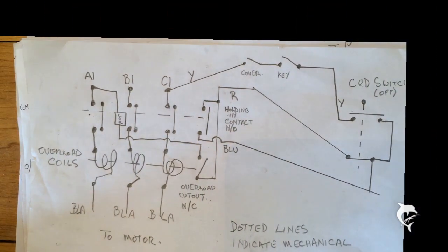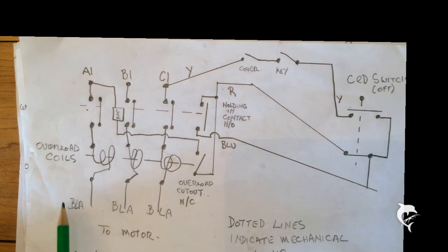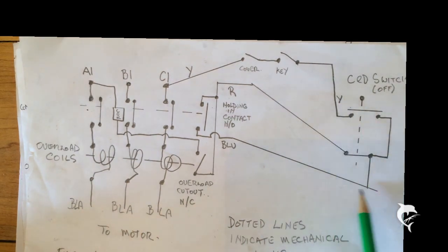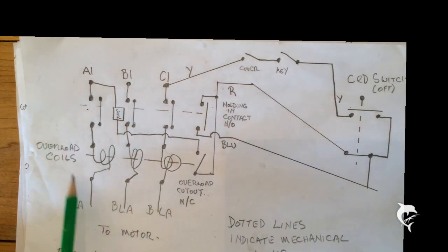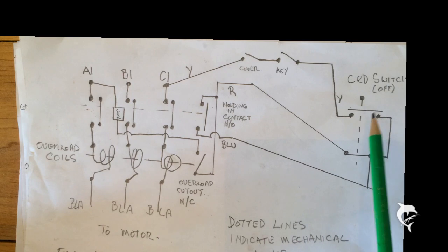Right people. The diagram you see here is a diagram I've drawn, which is of the starting circuit for a Colchester Student Mark 1. This is one I drew for Richard Kirkman on the Model Engineer Forum. We were trying to sort out how to get his student functioning again. This is the contactor and this is the remote stop start switch. Now, as you can see, the contactor is all in one place and the remote stop start switch is all in one place with the contacts shown as they actually work.